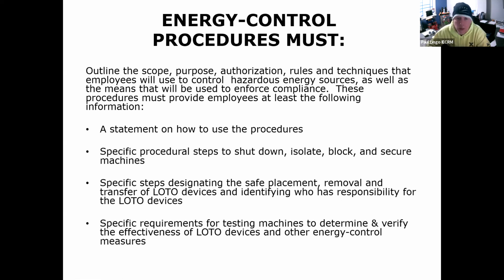There are only a few instances where OSHA allows it. OSHA says if the hazard of de-energizing that circuit creates a larger hazard than keeping it energized, then de-energizing should not be done. So there are instances in the electrical industry where we cannot turn it off, like hospitals, ventilating systems, and other special occupancies. In those cases we need to make sure we're adhering to PPE requirements and the policies of NFPA 70E in accordance with OSHA.